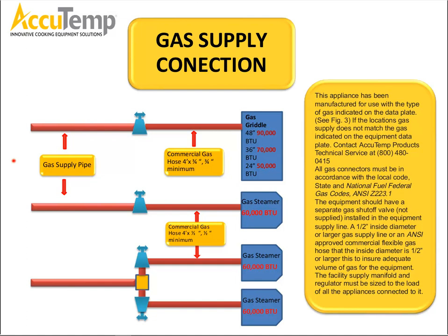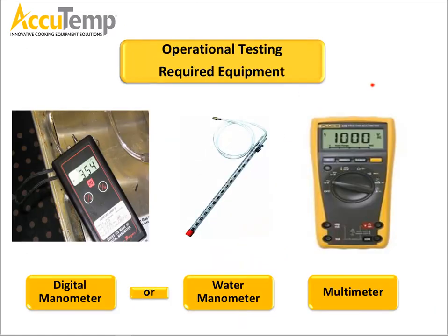So I am going to be talking a bit more about the internal checking of our equipment during the startup process. This is designed to be done once the unit is connected to power and gas, and if necessary with a steamer, the optional water inlet has also been installed. The slide we'll discuss first is just the vital pieces of equipment you'll need to complete the startup process with our equipment. You will need a multimeter capable of reading DC microamps. Most techs will carry a digital manometer, I'm sure. We do advise carrying a water manometer as well as a backup in case you see a gas reading that you're not quite sure about. Always good to get a second opinion on that.